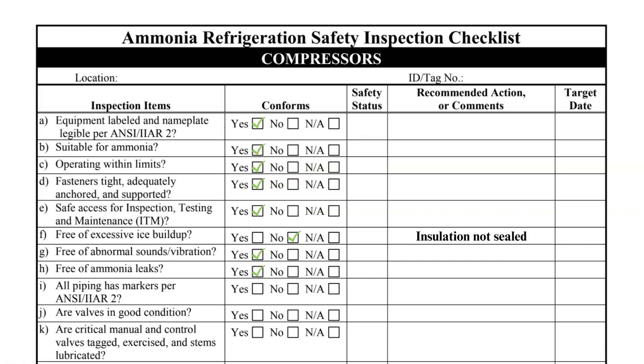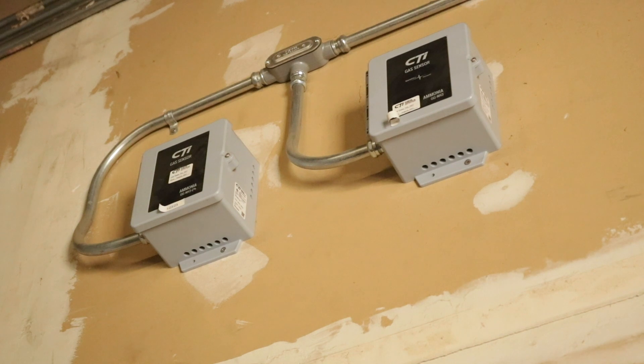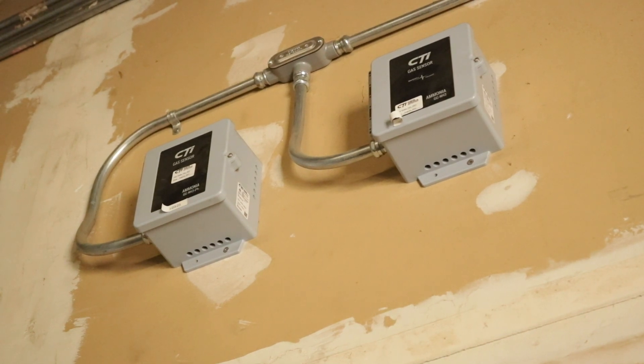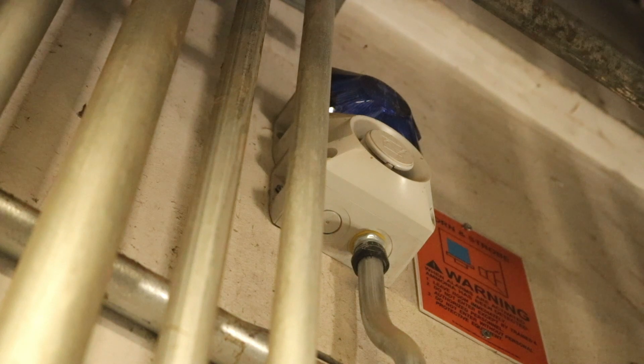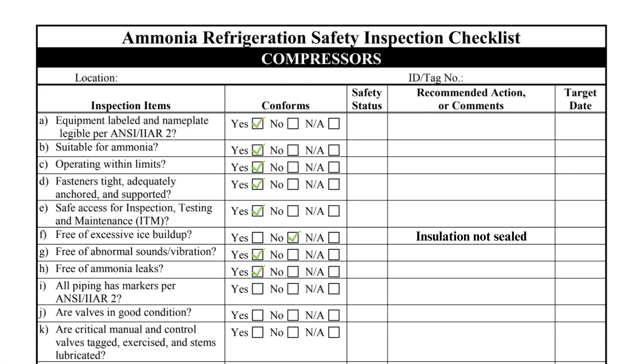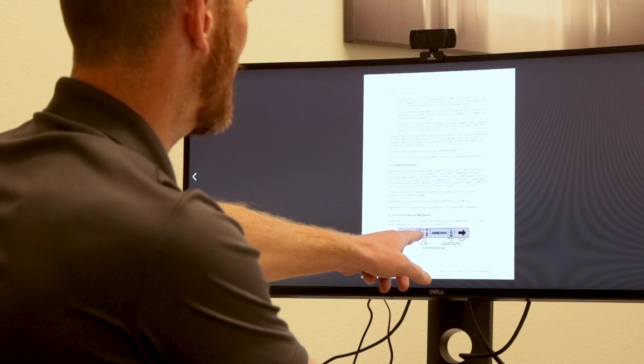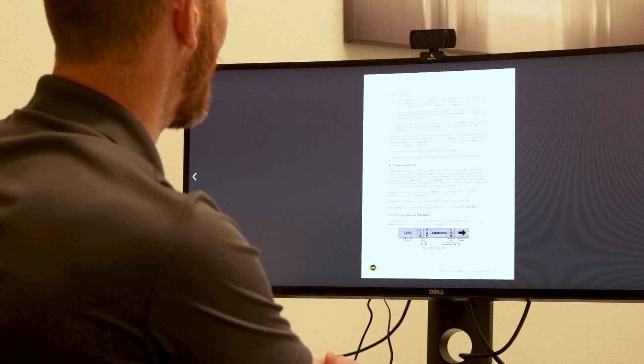Item H asks specifically about leaks. Compressors are typically located inside machinery rooms, which are required to be equipped with detectors and alarms. Item I inquires if the pipes are marked as required by IIAR Standard 2. Standard 2 requires piping mains, headers, and branches to be labeled with the following information.